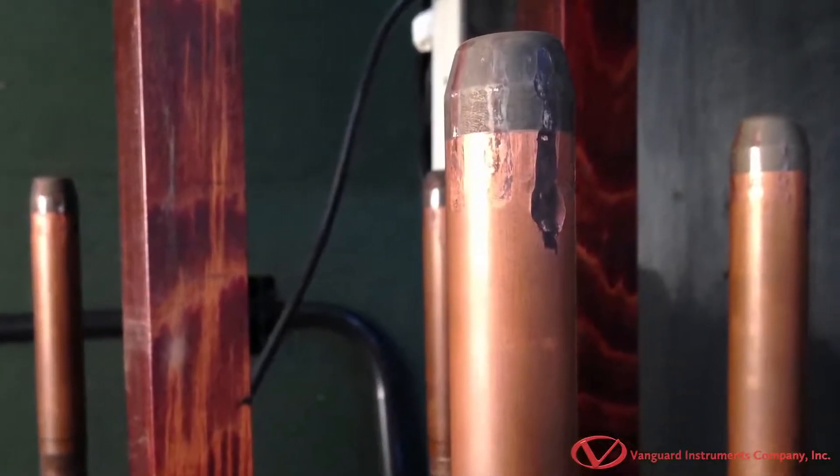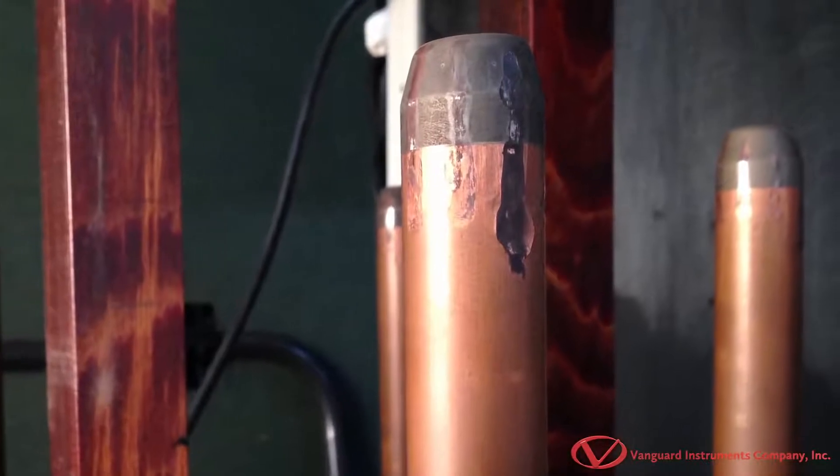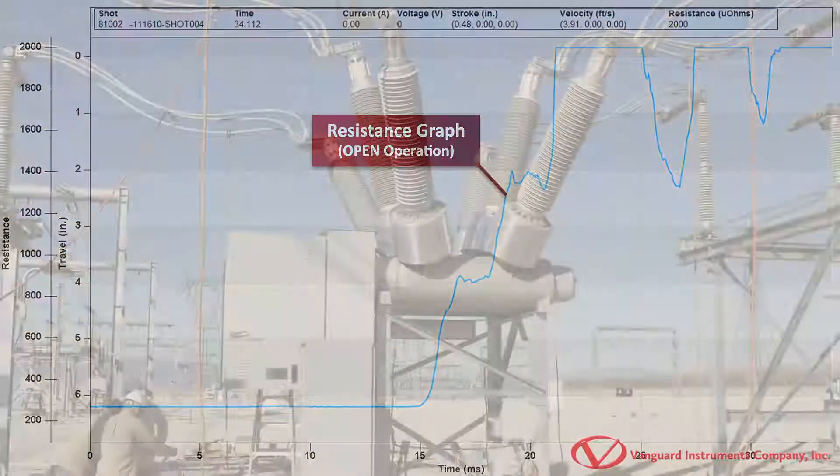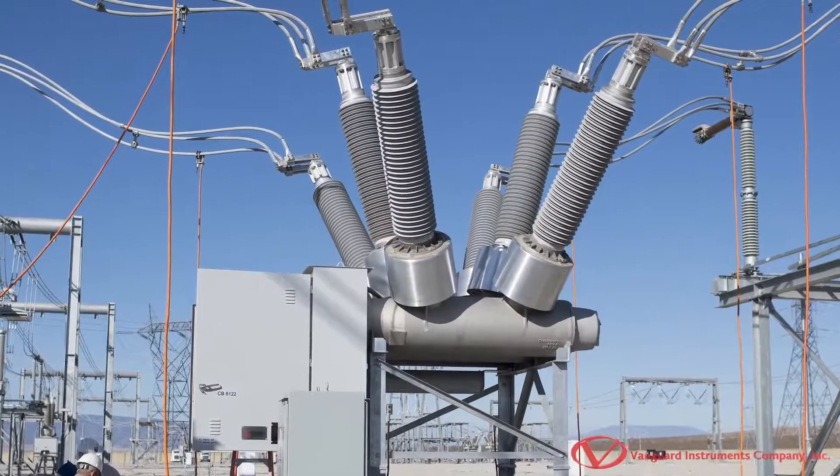Contact wear is also another important factor that can affect a breaker's performance. A dynamic resistance test can be performed and the resistance chart can be used to analyze the breaker's contact condition during the circuit breaker operation.